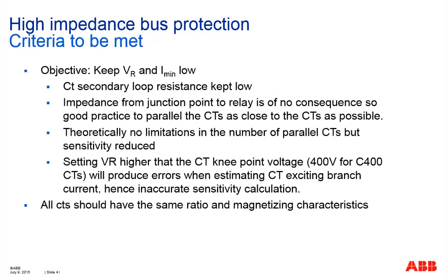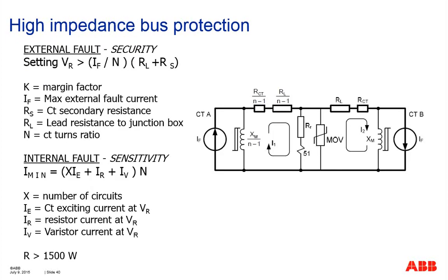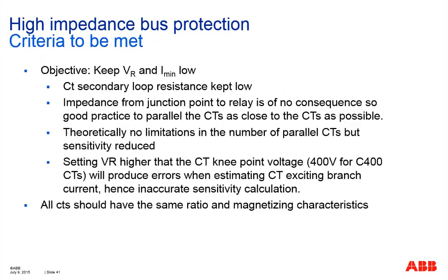to protect. The other thing is you want to keep the VR voltage low, because you don't want a high voltage here. For each cable on these leads between the CT and your relay, there is a certain rating on the cable insulation voltage, and you don't want to continuously stress it. There is also a safety consideration as well.